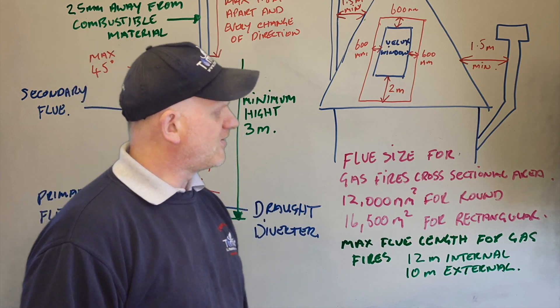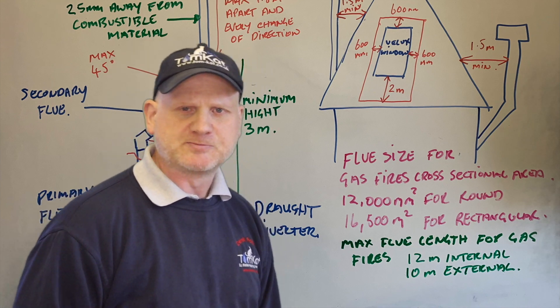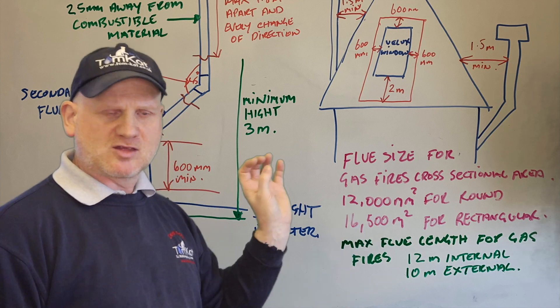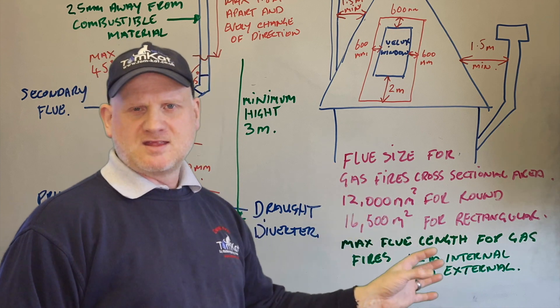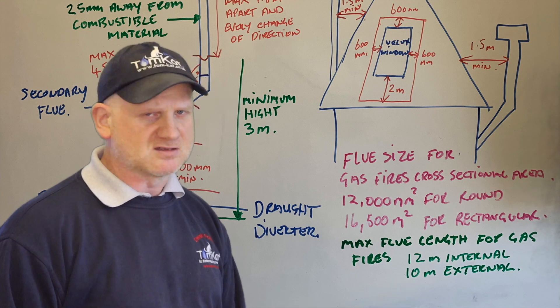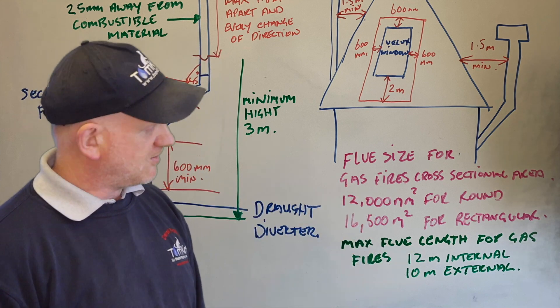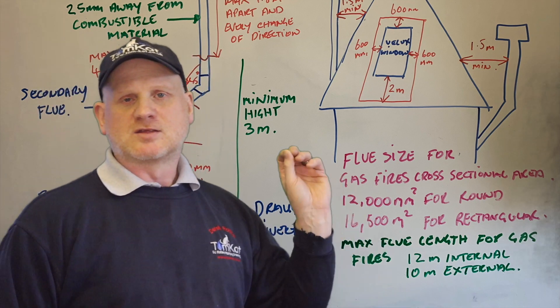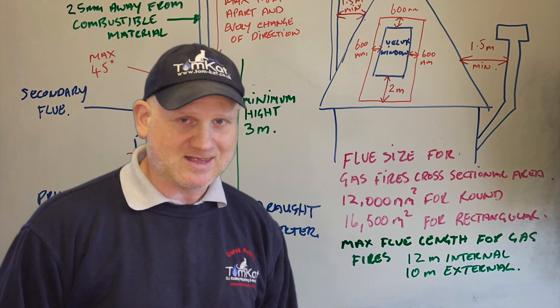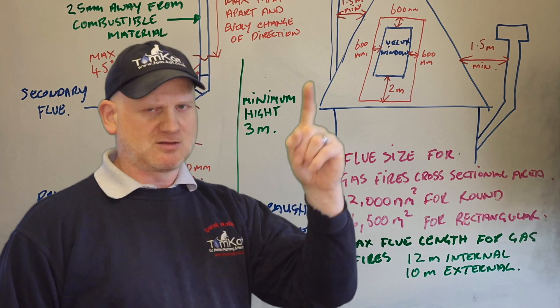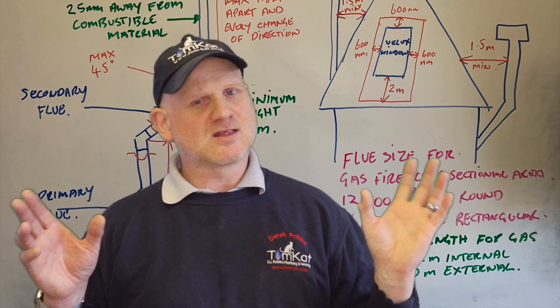For open flue fires, the cross-sectional area for a round flue is 12,000 square millimeters, and for a rectangular flue it's 16,500 square millimeters. The maximum flue length for a fire internally is 12 meters, and externally is 10 meters. Remember, if it goes outside and is longer than three meters, it still needs to be insulated.